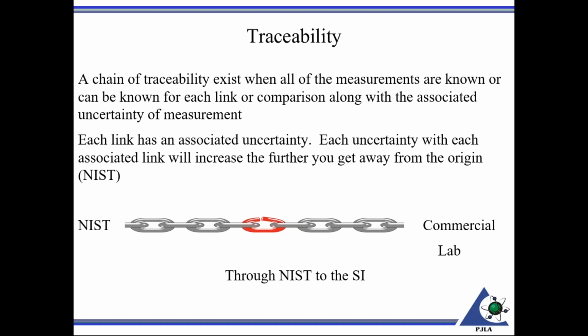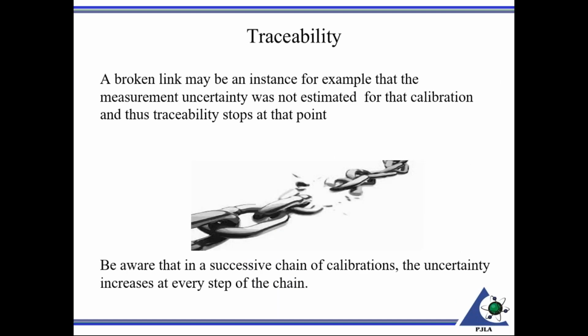Ideally, in the U.S., we like to say you're traceable through NIST to the SI unit. So ideally, the link at the back to NIST would be small. Each time you get further down that chain, you add to the uncertainty. Hence, each one of those links, if it was defined by its uncertainty, would be a little bit bigger, because they build upon the links that preceded them in this traceability chain that I'm attempting to depict here. A broken link may be an instance, for example, where a measurement uncertainty was not estimated for the calibration. Hence, the traceability would stop at that point.